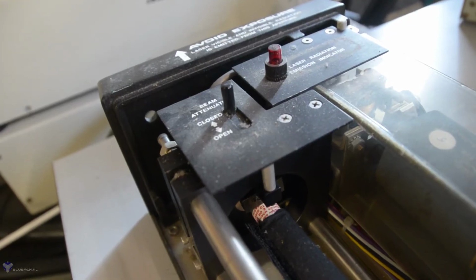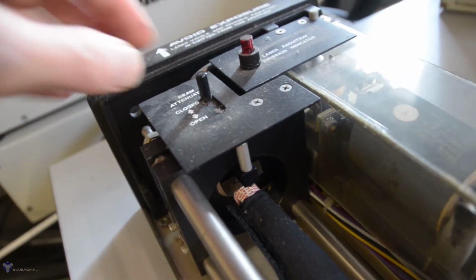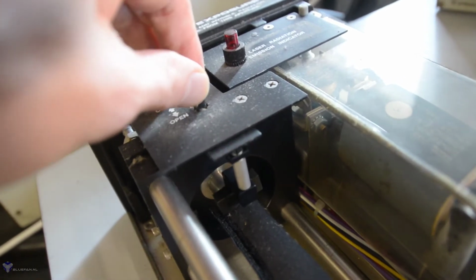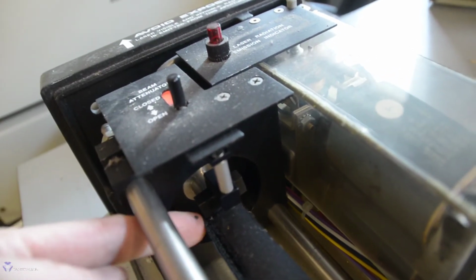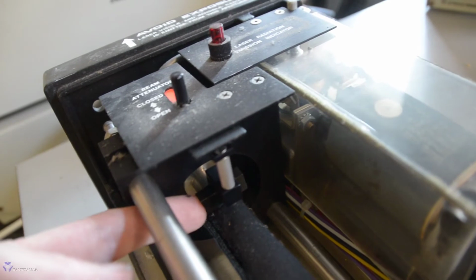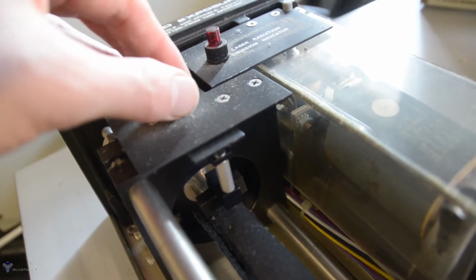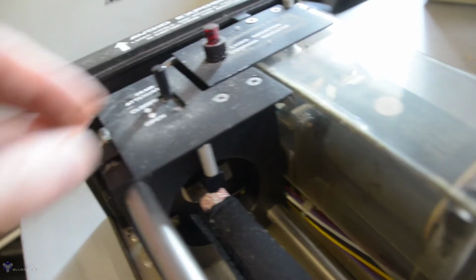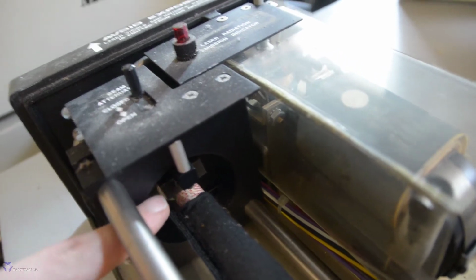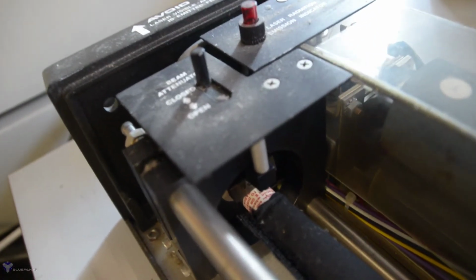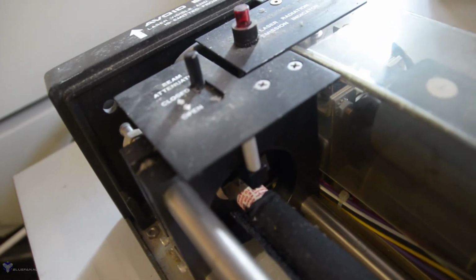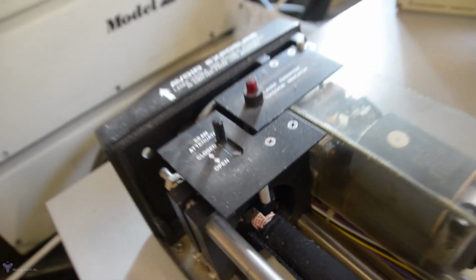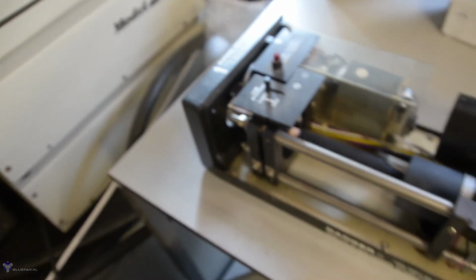One thing that's very neat on this laser is the shutter. If I move it from open to closed, you only see this part moving, but you don't see any actual shutter opening or closing. That's because this is a magnet. The actual shutter is inside the laser tube, inside the cavity. So this both keeps the shutter clean and free of dust, but also inside the cavity, once you block the laser, you don't have to dump all the power.